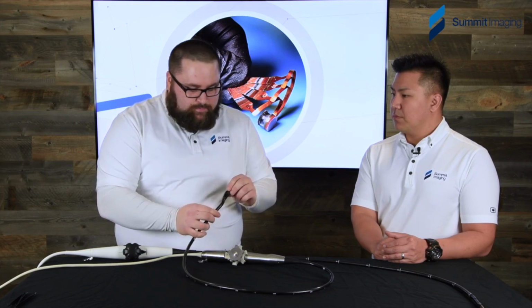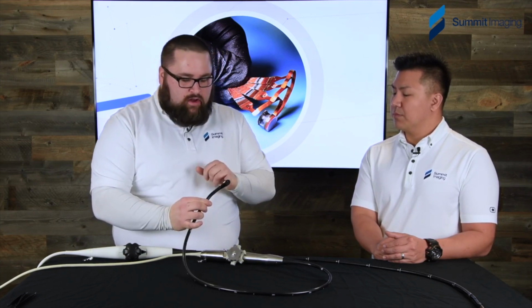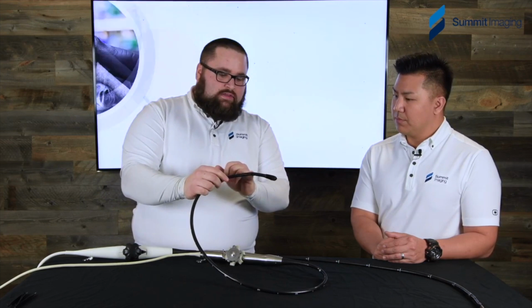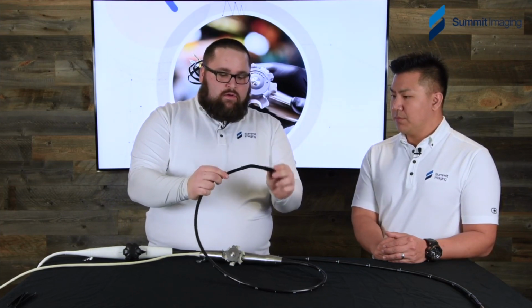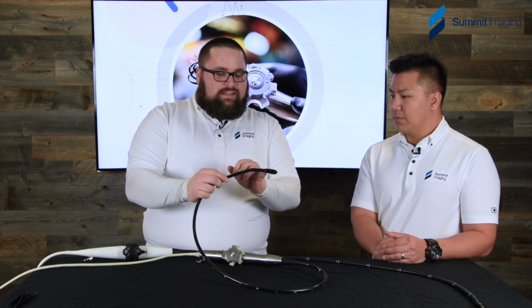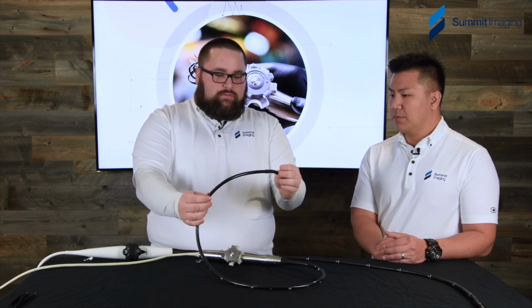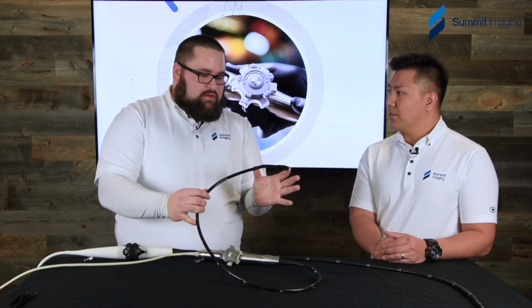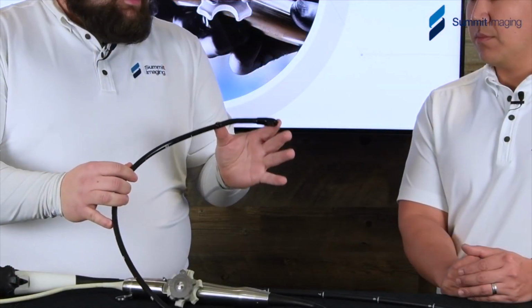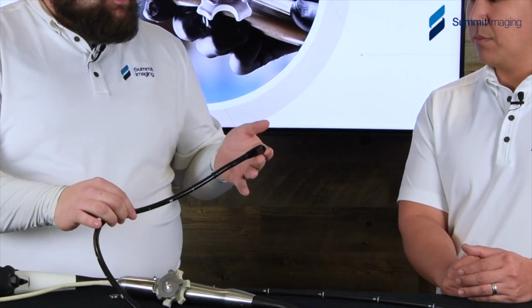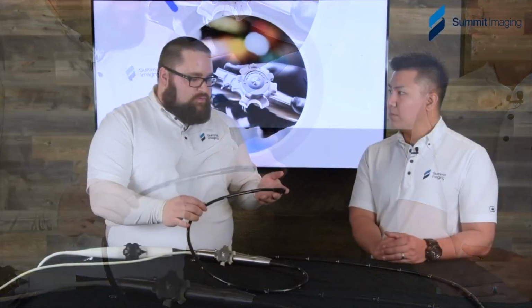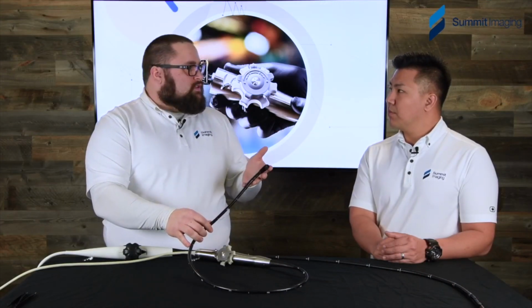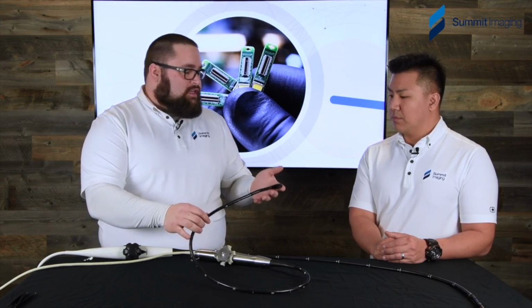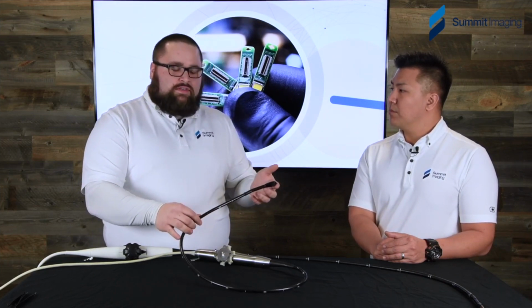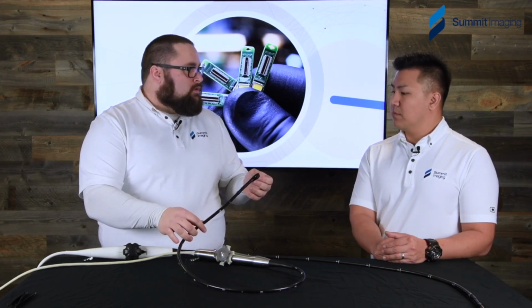transducers since we're going to talk about GE, Philips, and some of the others. But you'll have an array. It'll have a head, a distal steering area or control mechanism that is softer rubber, and then your actual tube. Now, this is your failure area right here. This is where a lot of your damage is going to occur. This is also where all your sensitive components are, and really where you want to be teaching places like central sterile or decontamination, or even your nurses in the OR where to look for problems.